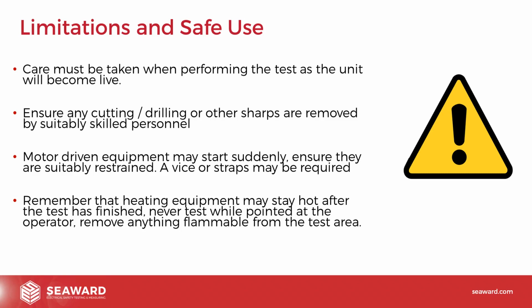When the test starts, again, it could start quite suddenly. So anything with motor-driven equipment, grinders for example, I've seen where you start the test off and these things start up instantly, they could start jumping around on the workstation. So it's generally recommended that if you can, you suitably restrain the device. Something like a vise or some straps may be required just to hold the device down nice and safely so it doesn't hop around when you start the test off.